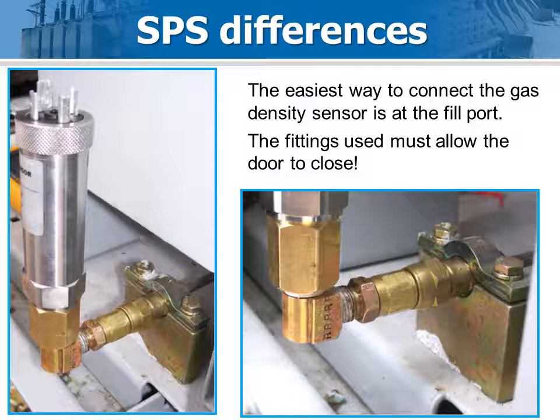The only major difference between the SP and SPS installation is how the gas density transducer is installed. On the SPS, shown here, the decision was made to install directly at the fill port. A custom adapter was fabricated. Door clearance was the only size constraint, so a close 90 was used.